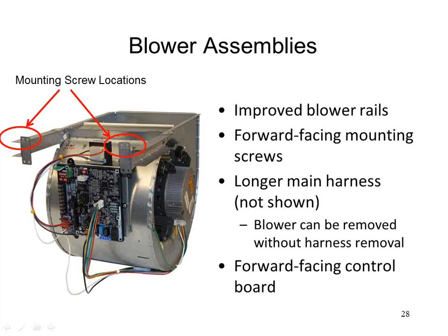Other modulating gas valves and other manufacturers' furnaces tend to only modulate upward, and they don't have the ability to modulate back downward. They don't have algorithms to do that. So they keep modulating upward as you need more and more heat, and then eventually the furnace would stage off, and then it would wait a cycle, and then it would stage on again and try to predict where to start based on its previous starting history and how much capacity it needed. Ours does not work that way.